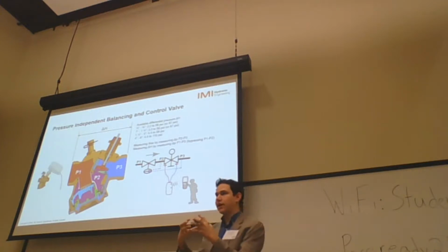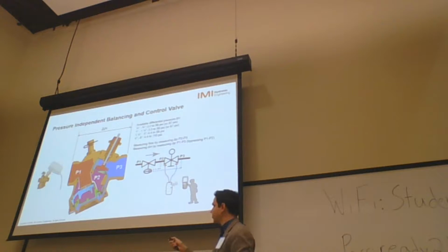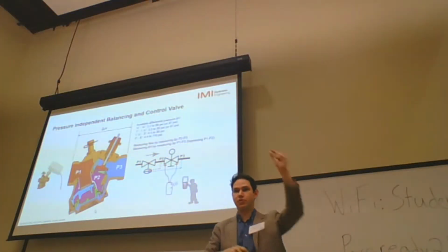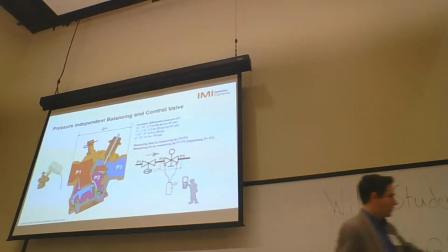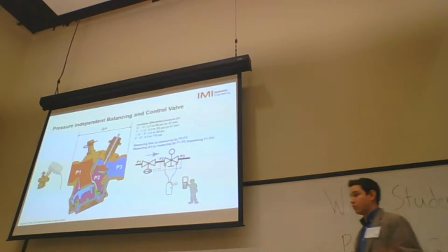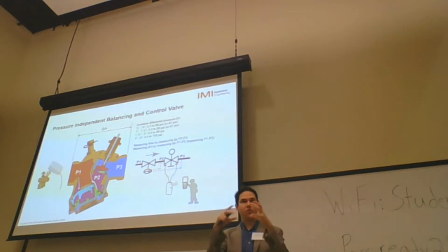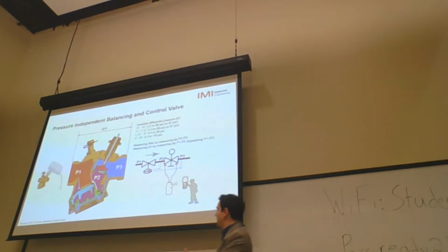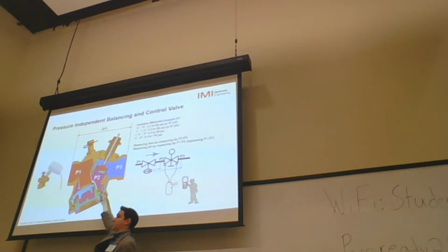in branches or directly at the control valve. If you look at this blue channel right there, this is the capillary tube that we saw before between supply and return of the branch, or this capillary tube right there, connecting supply and return of the branch. On a pressure independent control valve, that's everything on the same body, balancing, control valve, and differential pressure controller, the capillary tube is internal. So it's just a tiny channel that goes inside of the valve. But you have exactly the same things.